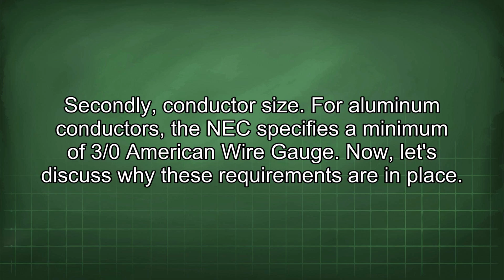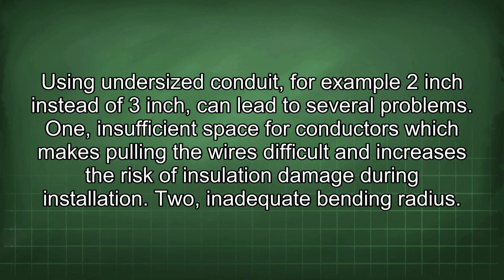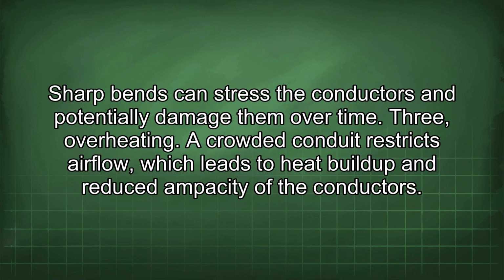Now let's discuss why these requirements are in place. Using undersized conduit, for example 2-inch instead of 3-inch, can lead to several problems. 1. Insufficient space for conductors, which makes pulling the wires difficult and increases the risk of insulation damage during installation. 2. Inadequate bending radius. Sharp bends can stress the conductors and potentially damage them over time. 3. Overheating. A crowded conduit restricts airflow, which leads to heat buildup and reduced ampacity of the conductors.